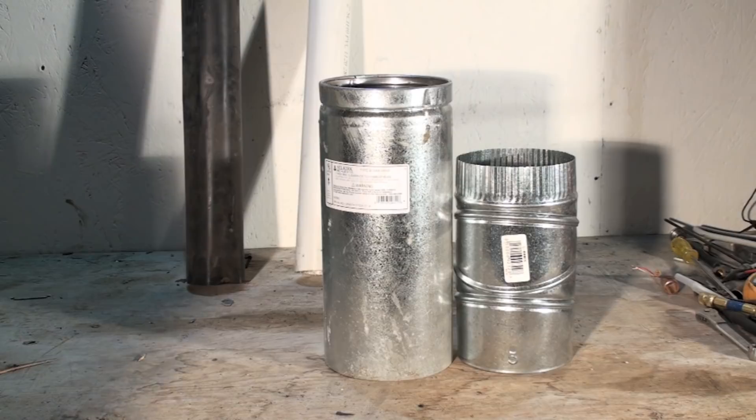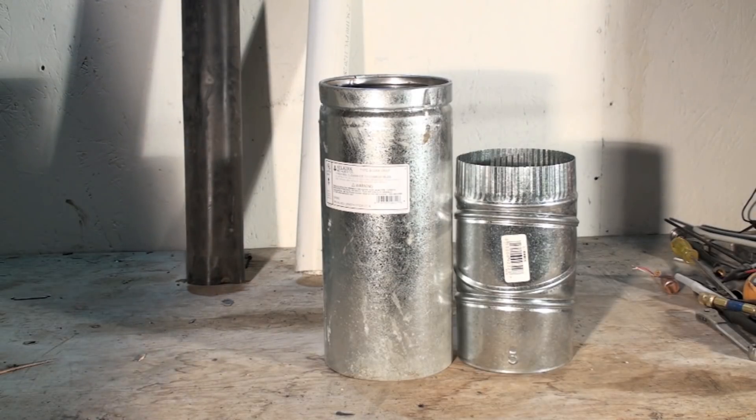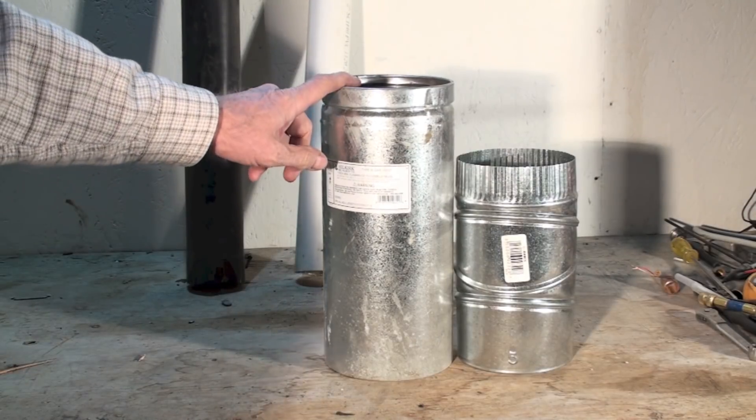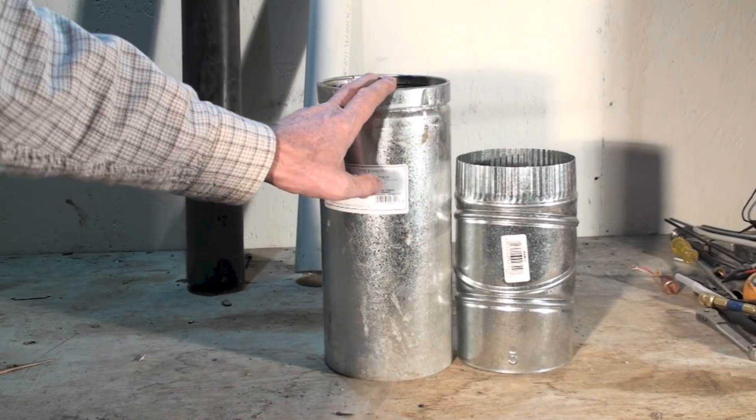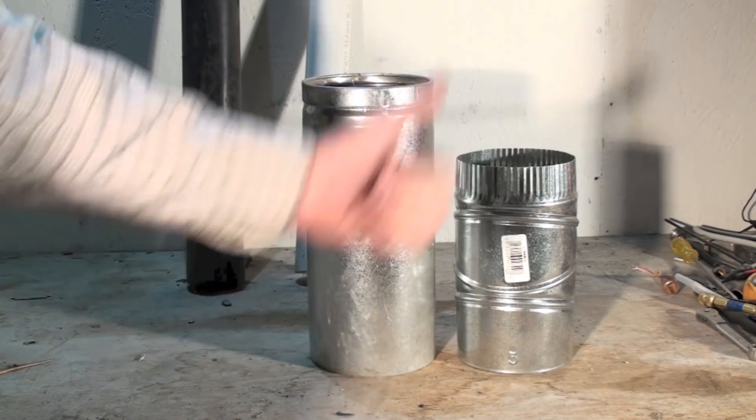When we started getting high efficiency furnaces, we changed from what we used to call the 80% furnace, which was kind of a steady state rating. That was the steady state supposed efficiency. We started going over to higher efficiency furnaces. The higher efficiency furnaces, we could still use B-Vent. And by the way, this vent all had to pitch upwards, minimum quarter inch per foot.